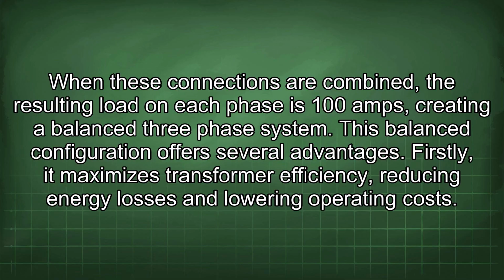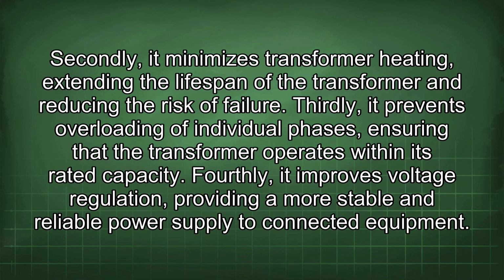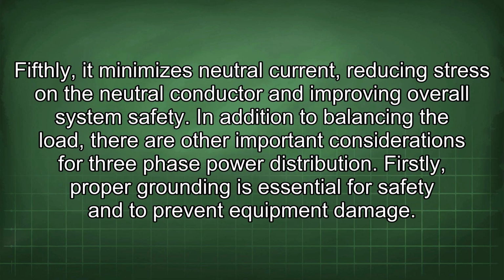This balanced configuration offers several advantages. Firstly, it maximizes transformer efficiency, reducing energy losses and lowering operating costs. Secondly, it minimizes transformer heating, extending the lifespan of the transformer and reducing the risk of failure. Thirdly, it prevents overloading of individual phases, ensuring that the transformer operates within its rated capacity. Fourthly, it improves voltage regulation, providing a more stable and reliable power supply to connected equipment. Fifthly, it minimizes neutral current, reducing stress on the neutral conductor and improving overall system safety.